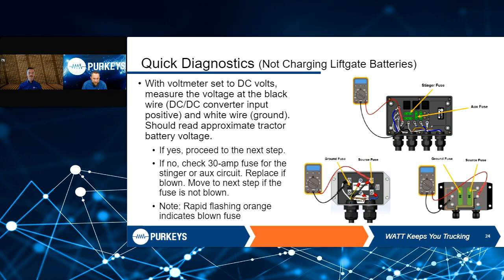So, some quick diagnostics for this: with a voltmeter set to DC volts, measure the voltage on the black wire. The black wire is going to be your input wire, and your white wire is going to be the ground. It should read approximately tractor battery voltage. And this just shows all the examples of where to check that voltage. If yes, proceed to the next step.